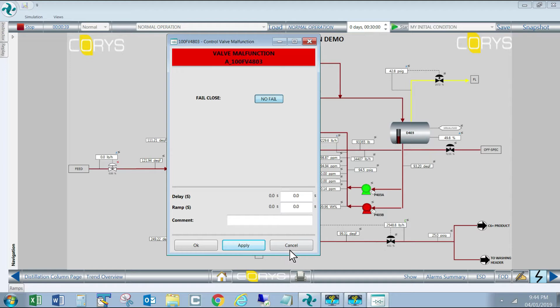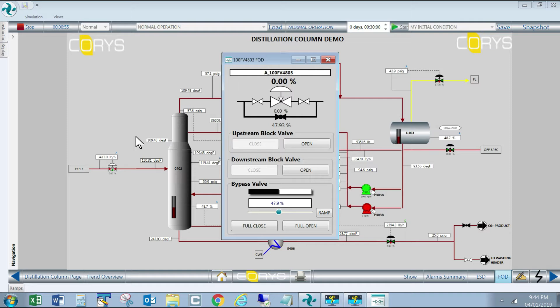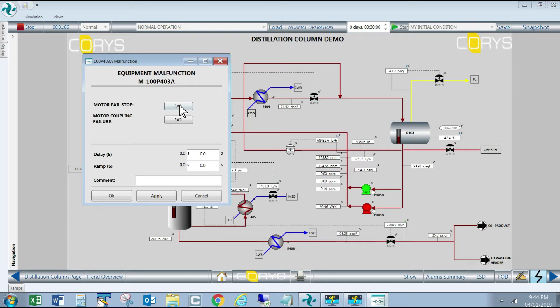So this is the situation where they can operate the bypass valve to operate the process. So basically isolate the control valve and then use the bypass valve to operate the process as close as possible to normal operation. Other failures are pumps, like all motor driven equipment, like a pump can be fail stopped.